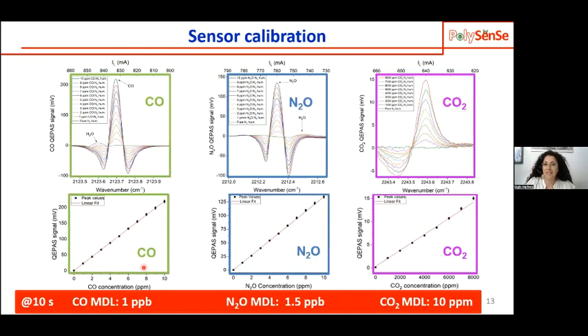Again, we started with the sensor calibration. We employed a gas cylinder of 10 ppm of carbon monoxide in humidified nitrogen, 10 ppm of N2O in humidified nitrogen, and a CO2 cylinder of 10,000 ppm, so 1% of CO2. We diluted this concentration in order to verify the linearity of the sensor responsivity with the concentration of the gases. And for a lock-in integration time of 10 seconds, we obtained minimum detection limits of 1 ppb for CO, 1.5 ppb for N2O, and 10 ppm for CO2.